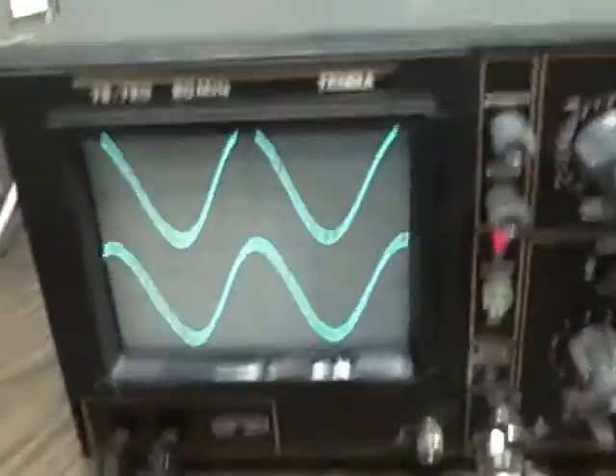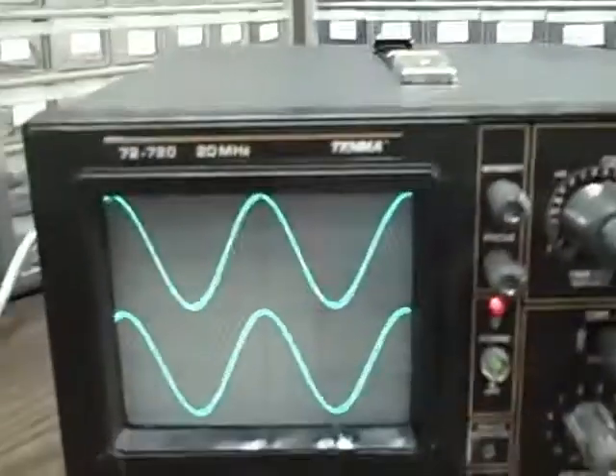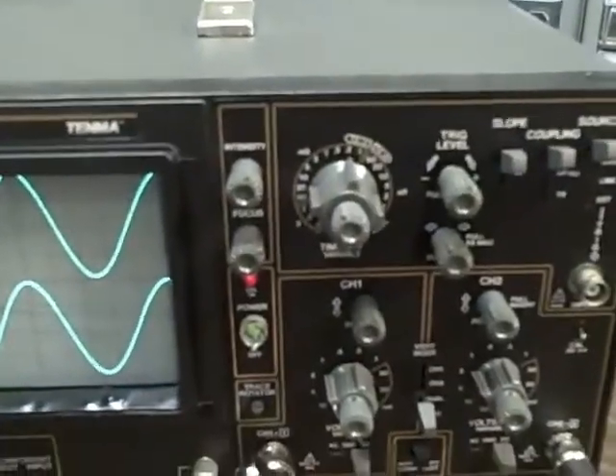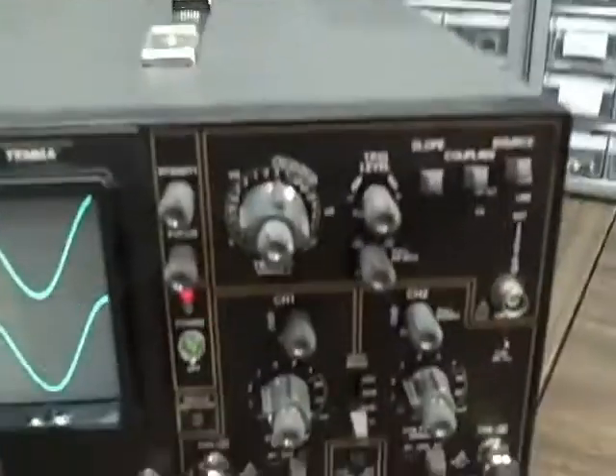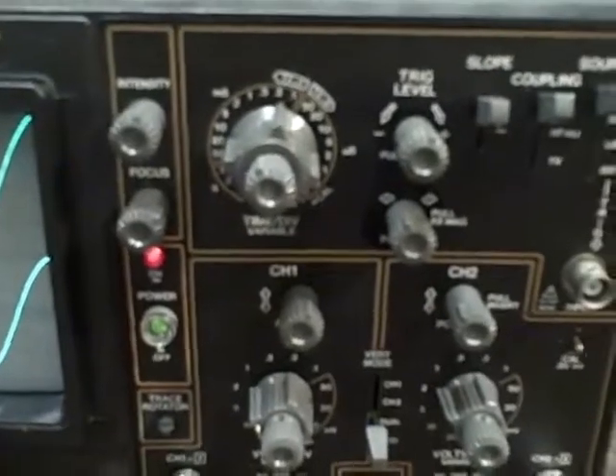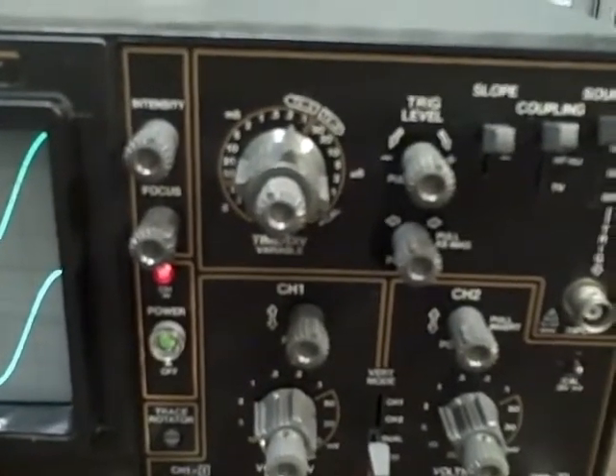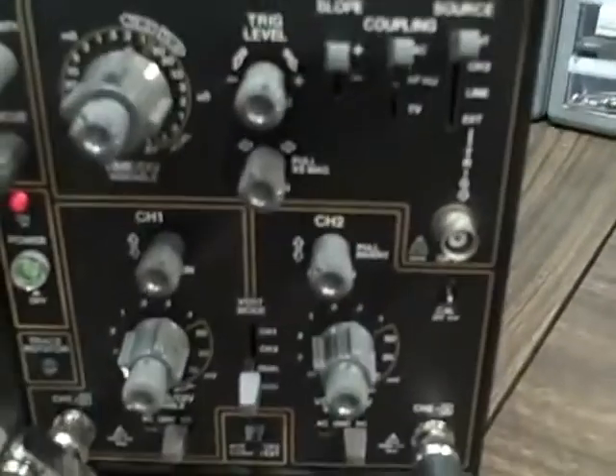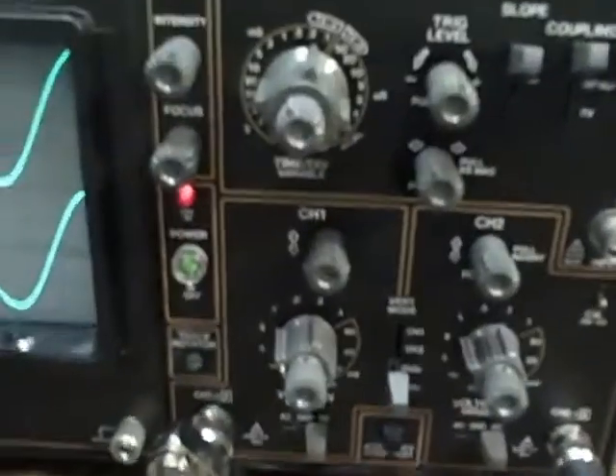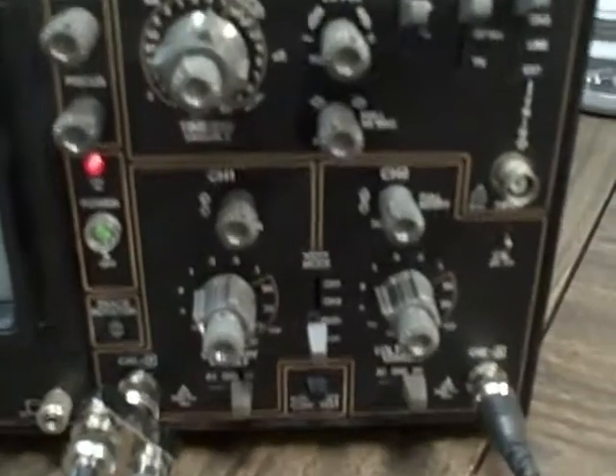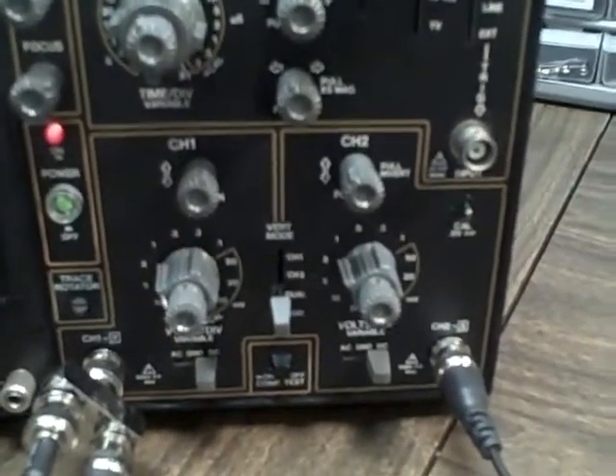That's unfortunate because it's a wonderful scope and to have its look harmed in any way is a shame, but that's the way it is. Overlooking that, it's a very nice scope. We have the scope covers 0.5 seconds per division on horizontal trace maximum to a minimum of 0.2 microseconds per division in 20 steps, and then there's a 21st step on the range switch that's an XY position.